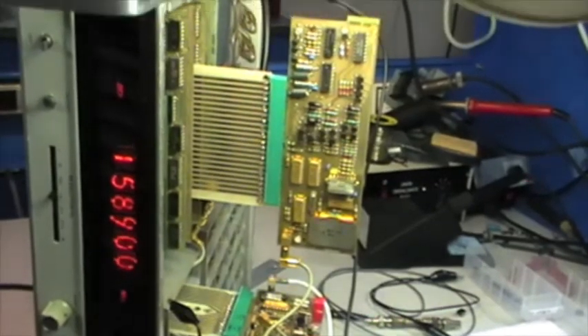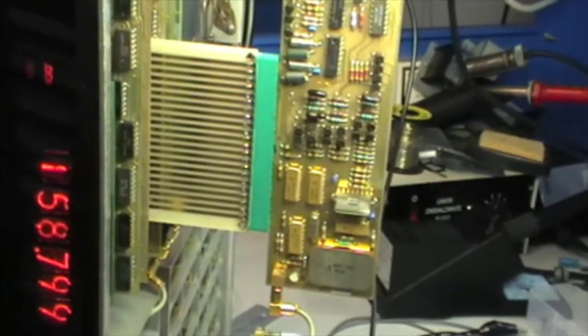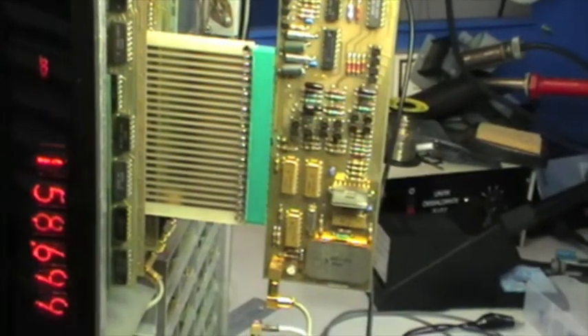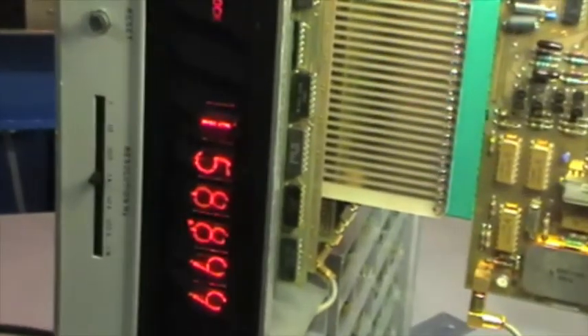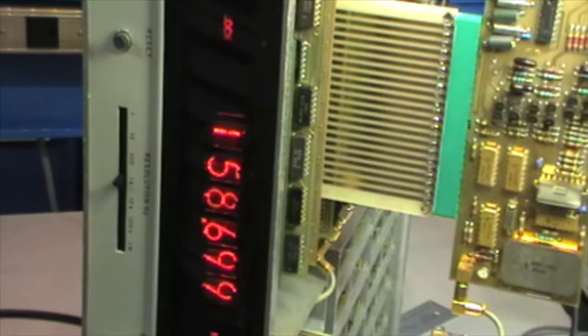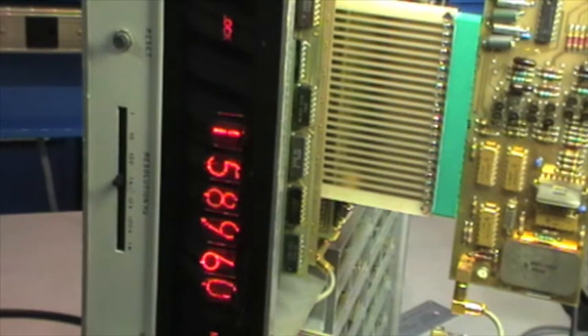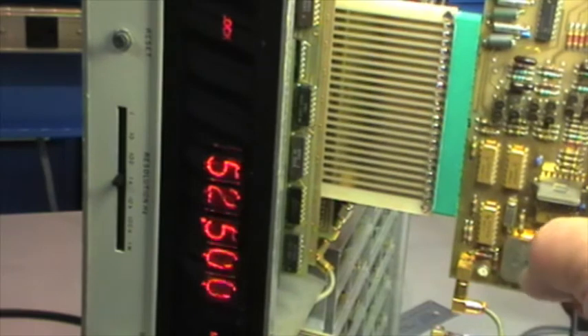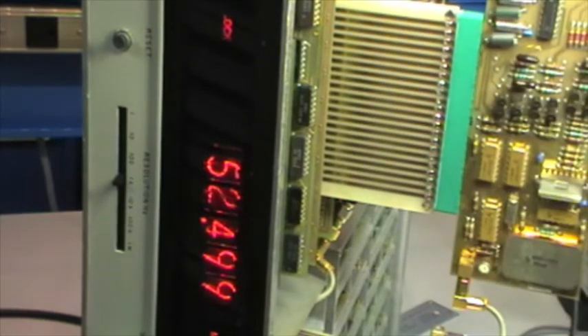This is A22 exposed using the extended board, and look at the display. This is something that I have discovered right in this moment. My signal generator is now set to 250 megahertz, and it's reading 50, and also it's not really stable, right? Perhaps because I have moved this out from there, because before it was really stable. And if I increase by 100 and set to 350 megahertz, look at that, 150. So it seems that it's missing two counts.